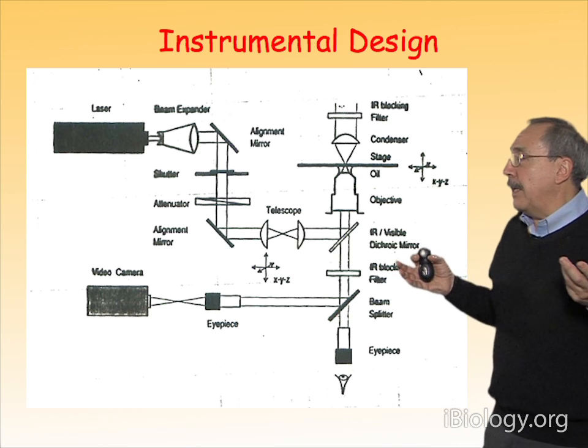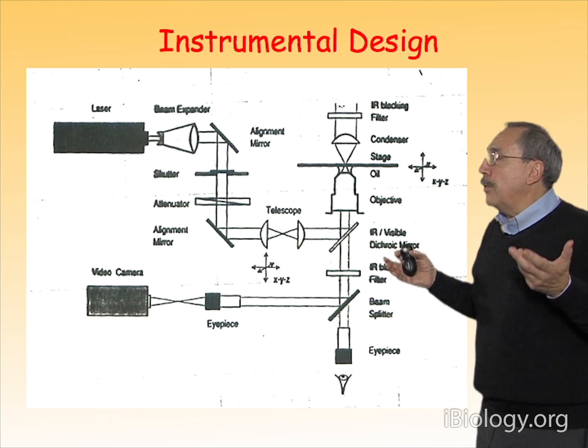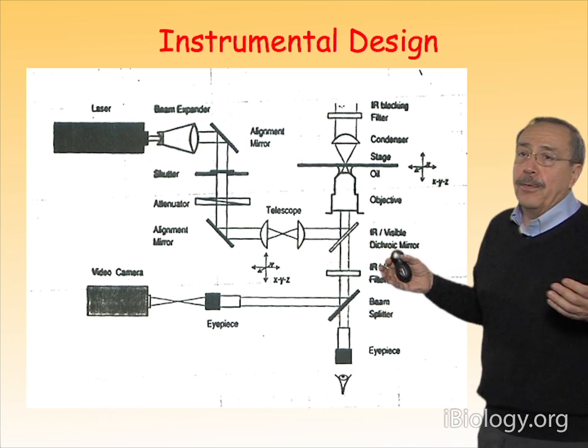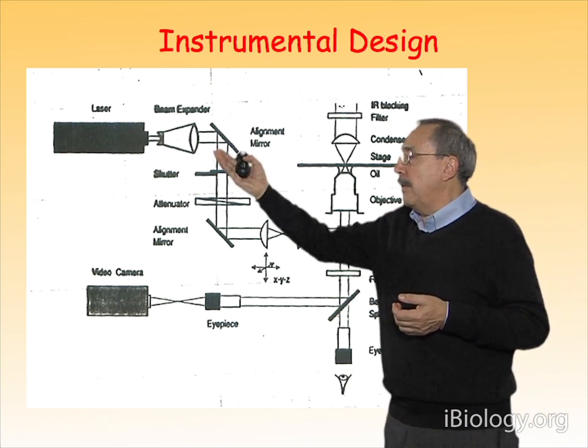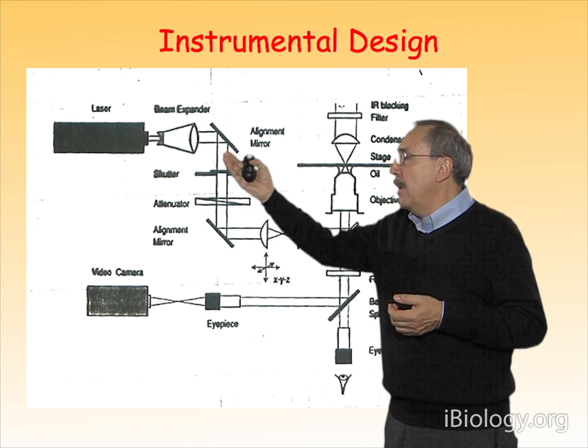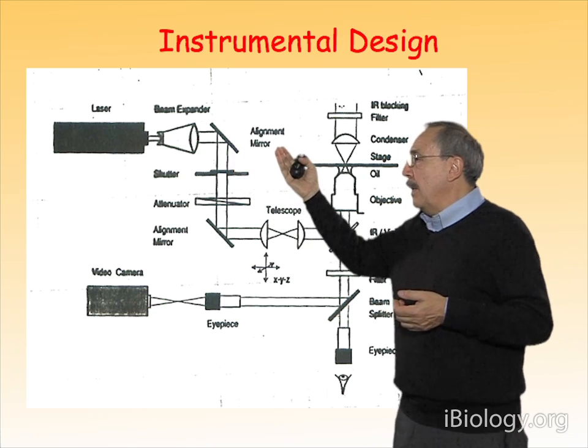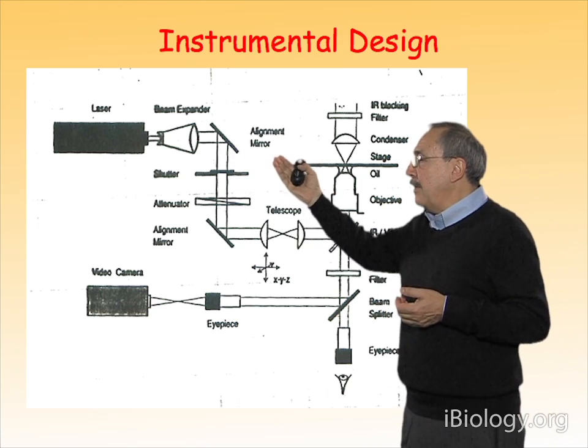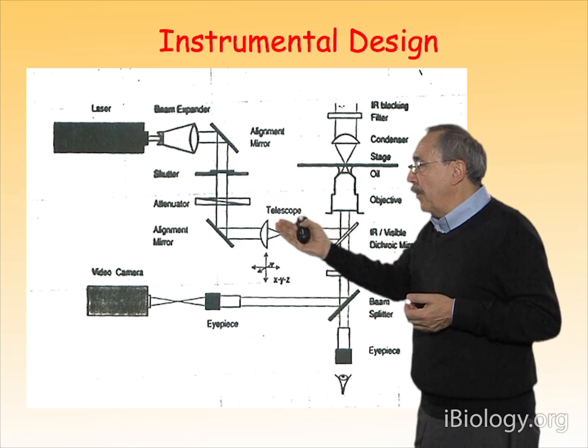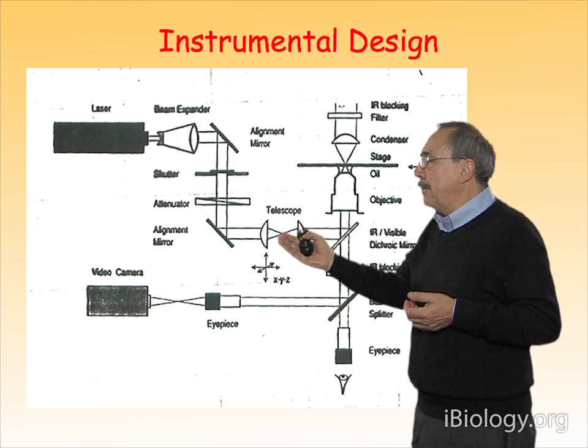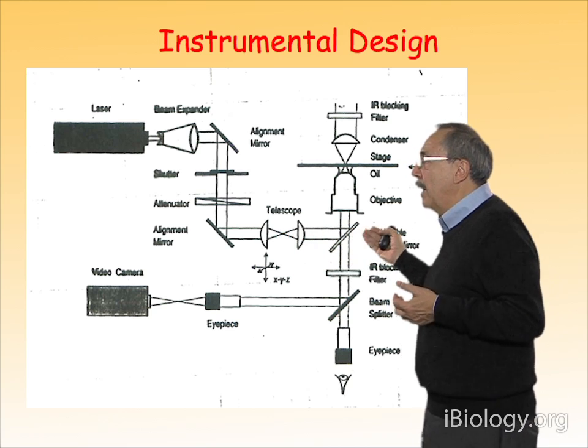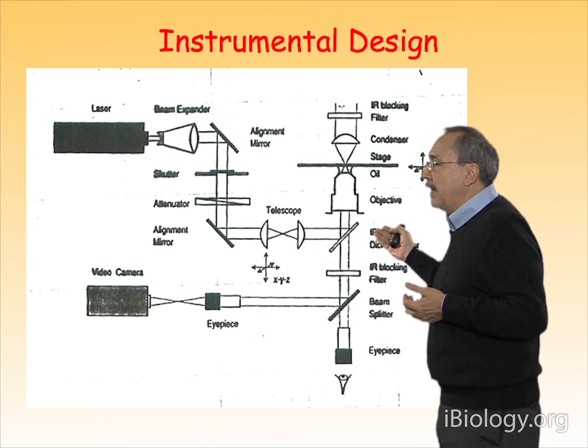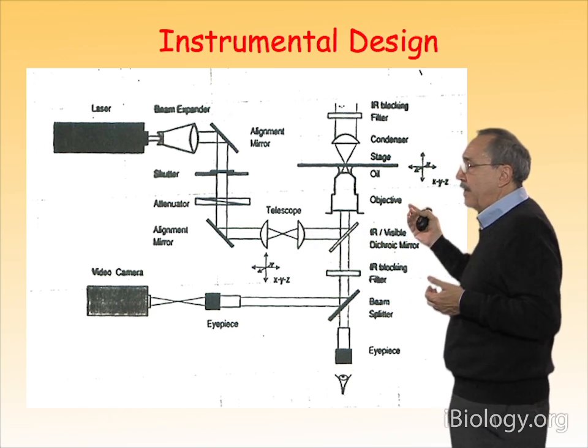The design of an instrument that actually carries out optical trapping is quite simple. All you need is a source of light, in this case a laser. You can then span that laser through a number of optical pieces, and eventually you will fill the back focal plane of an objective lens, as shown here.